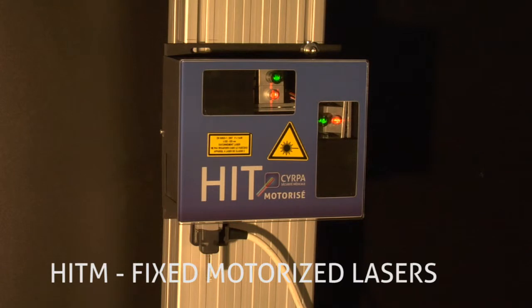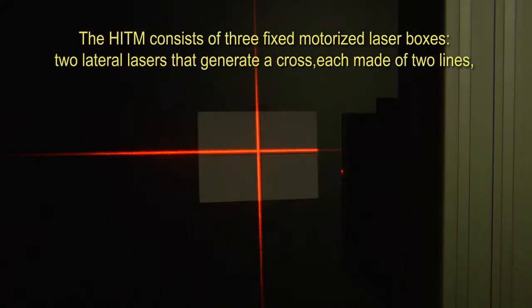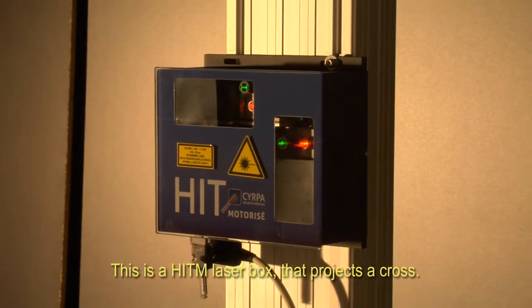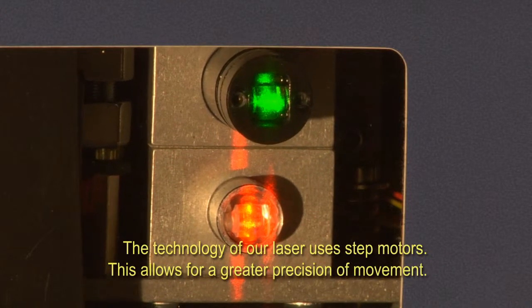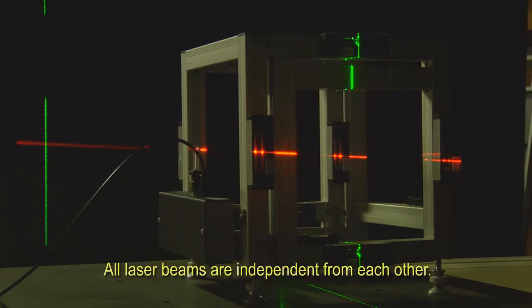CYRPA also offers a fixed motorized laser system used in the treatment room: the HIT M. The HIT M consists of three fixed motorized laser boxes — two lateral lasers that generate a cross each made of two lines, and one sagittal laser that generates one line. This is a HIT M laser box. The technology uses step motors, allowing for greater precision of movement. The laser lines can move on all three fundamental movements: translation, rotation, and tilt. All laser beams are independent from each other.